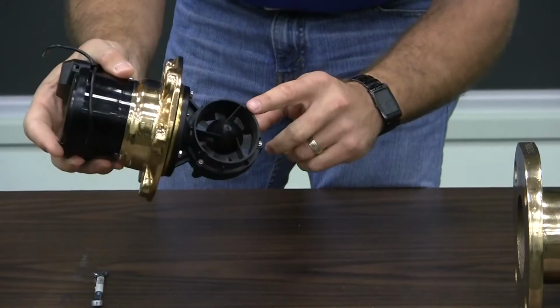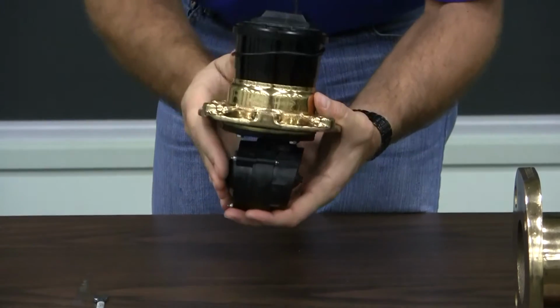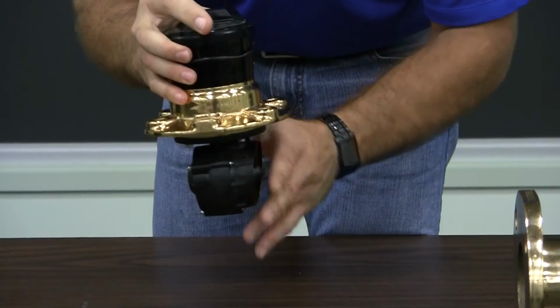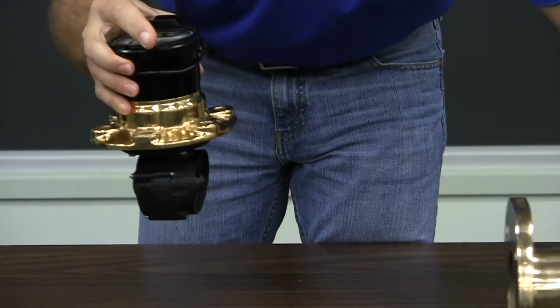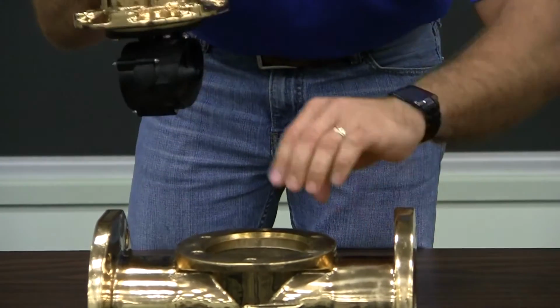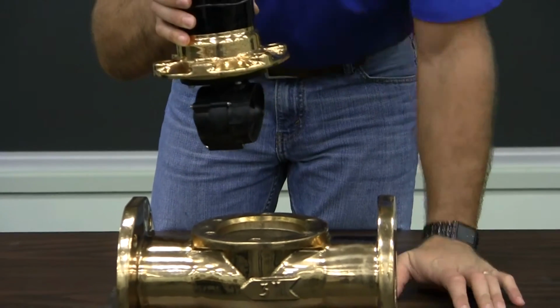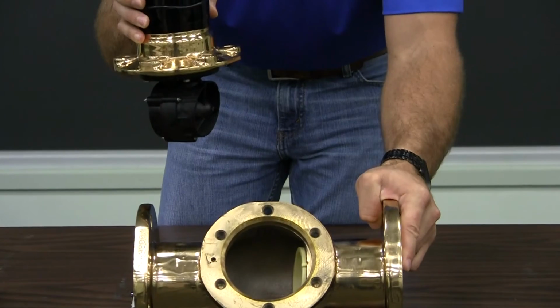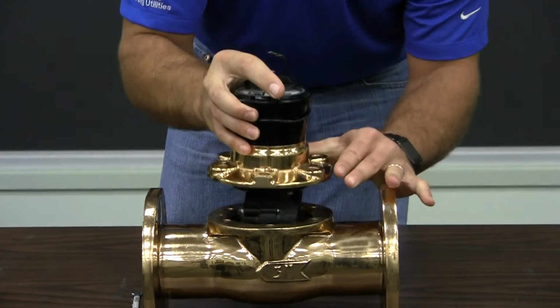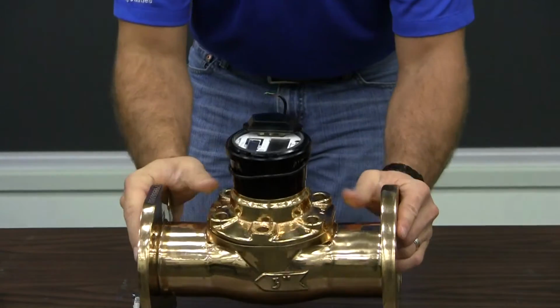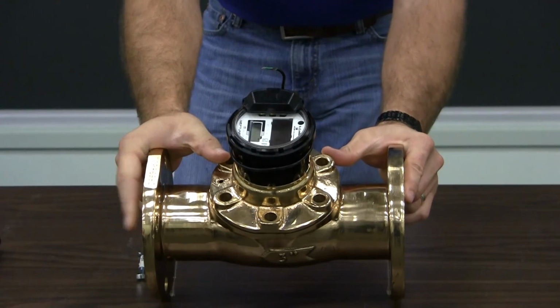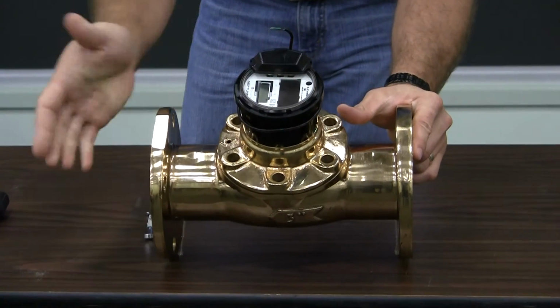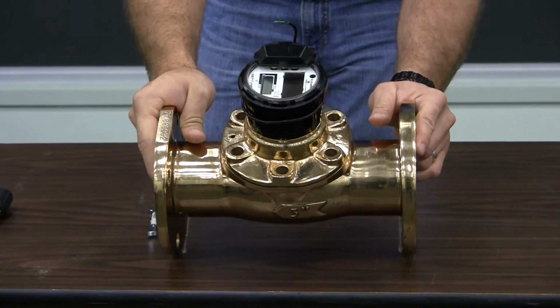Now, remember there was a slanted face and a flat face of a turbine element. The slanted face is the inlet side of the turbine meter. So when you go to put it back in the meter, this slanted face is just going to seal against that seal tube we placed in there earlier. Now we've dropped it in, we'll put in the remaining cover bolts, and we've completed the breakdown session for the 3-inch HP turbine.